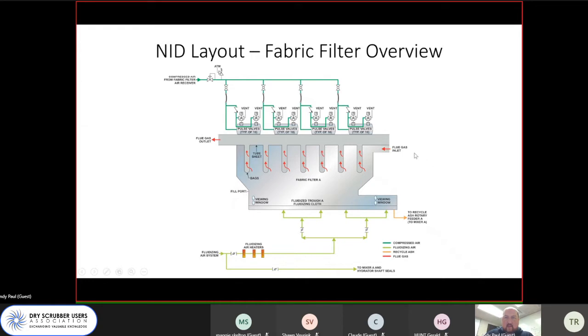We have flue gas coming in, going through the fabric filter materials, which are located here. It's a pulse jet system, so as we remove ash, it falls into the fluidizing trough. From the fluidizing trough, we remove a small portion and send that out to our ash silo, which helps us inject new material. The majority is recycled through the process and goes to the rotary ash feeder I pointed to on the last page. This is a key component for us to minimize reagent usage, being able to optimize the amount of recycled ash we can use.